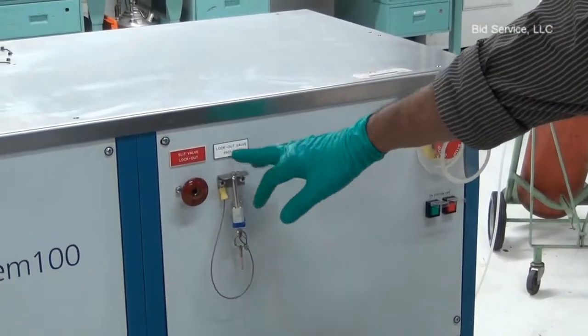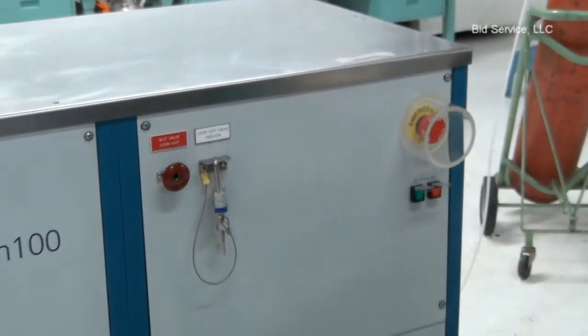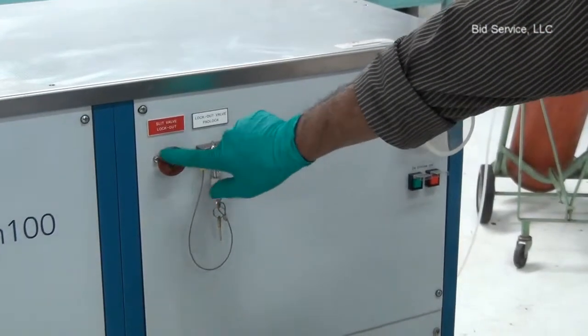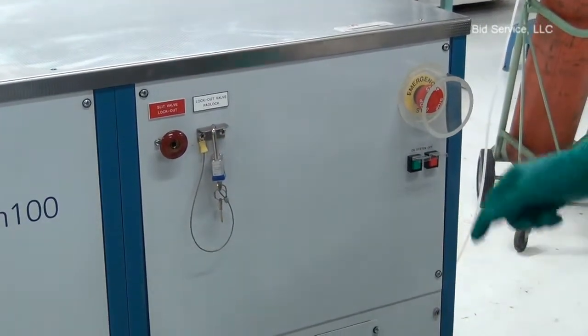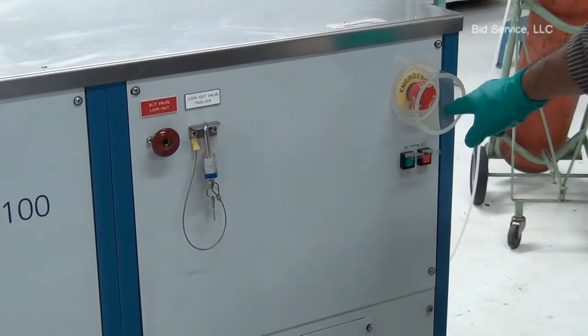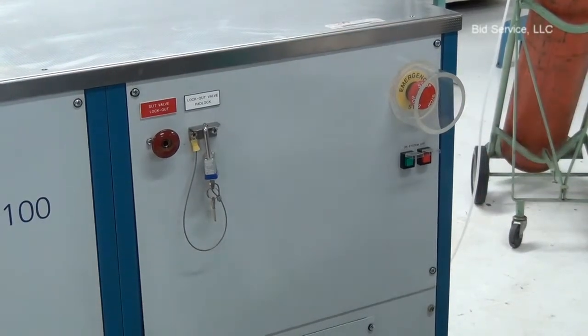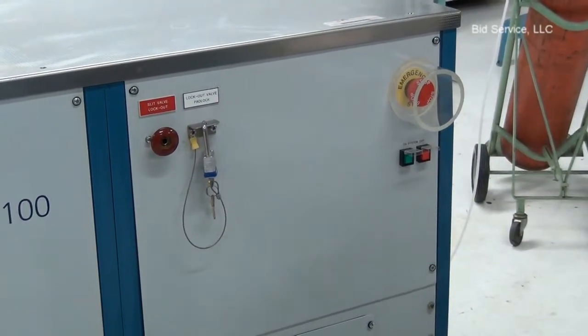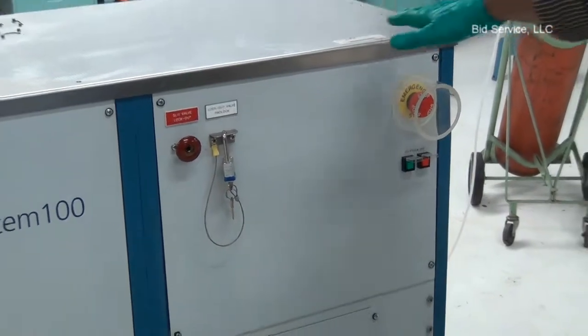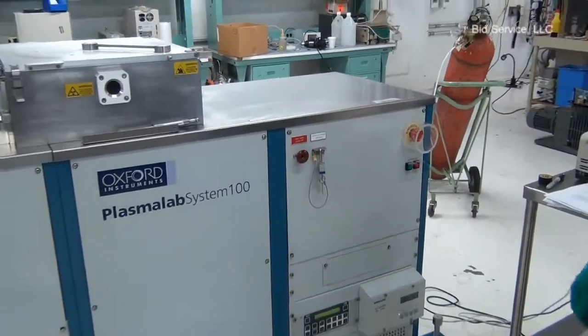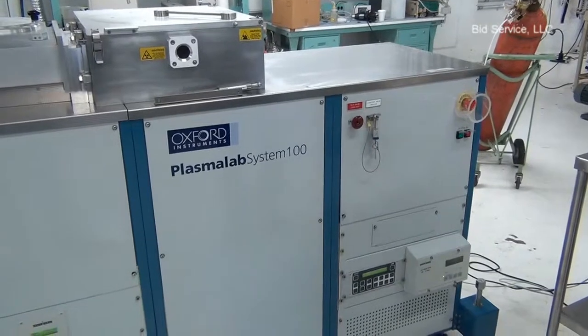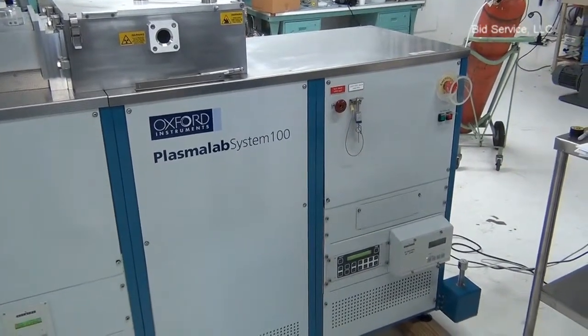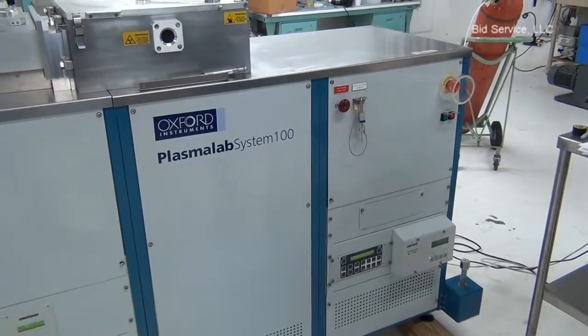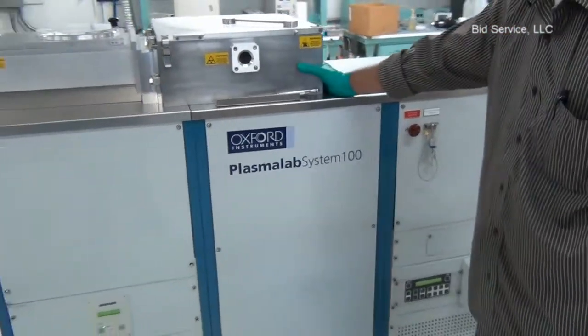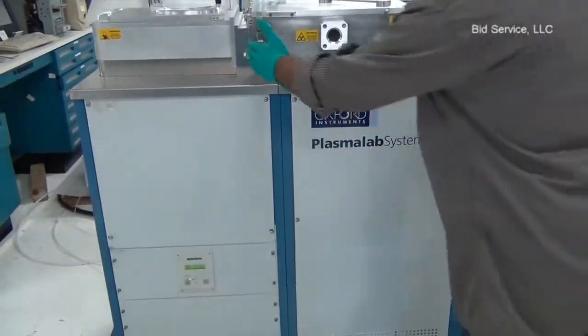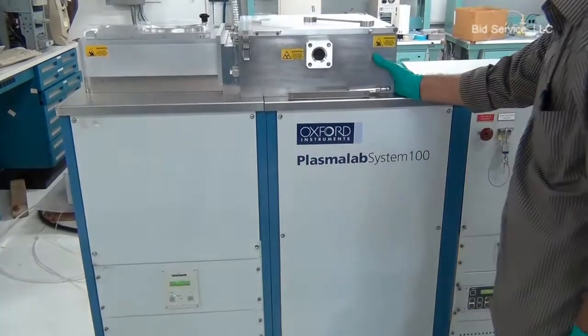These are the lockout valve to make it tamper-proof. This is a pneumatic switch for emergency shutdown, and this is the emergency shutdown to turn off the system. And the main turbo molecular pump is water-cooled. Also, the chamber valve, these valves are also temperature controlled.